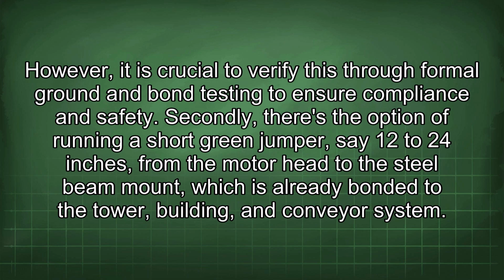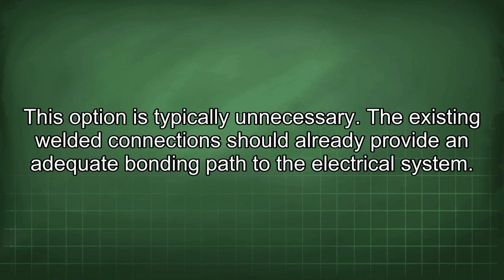Secondly, there's the option of running a short green jumper, say 12 to 24 inches, from the motor head to the steel beam mount, which is already bonded to the tower, building, and conveyor system. This option is typically unnecessary. The existing welded connection should already provide an adequate bonding path to the electrical system.